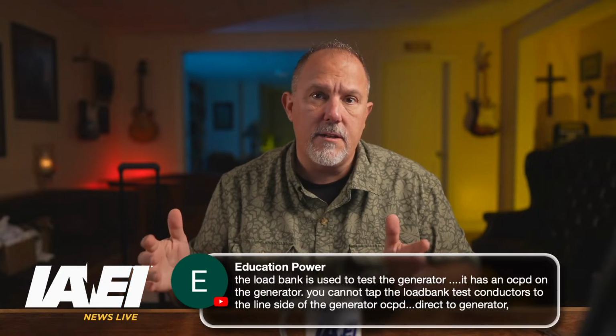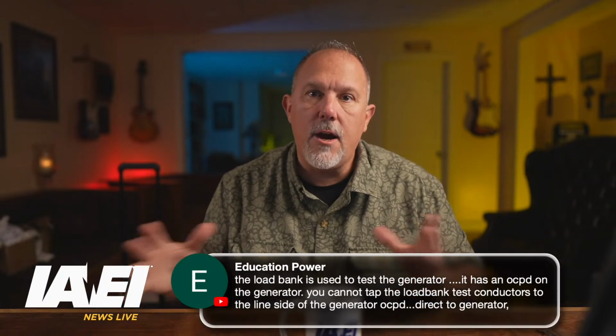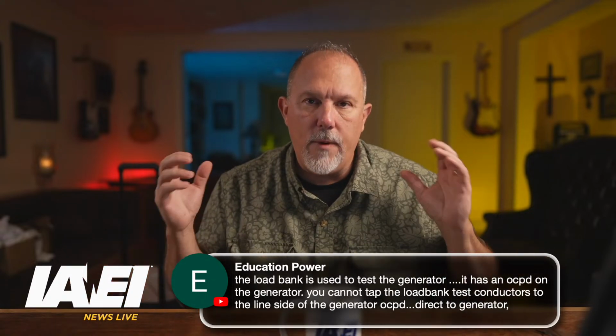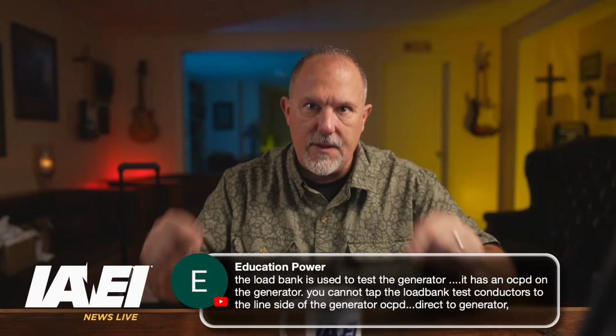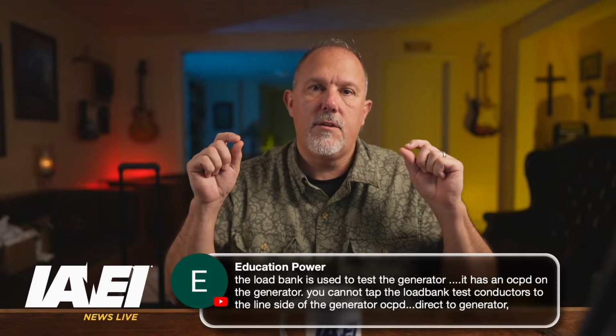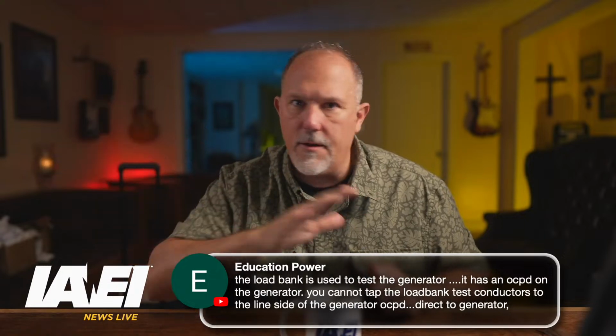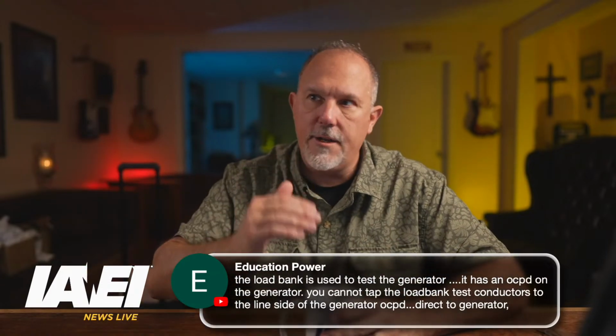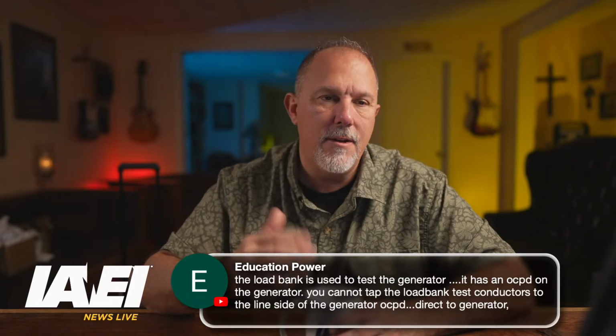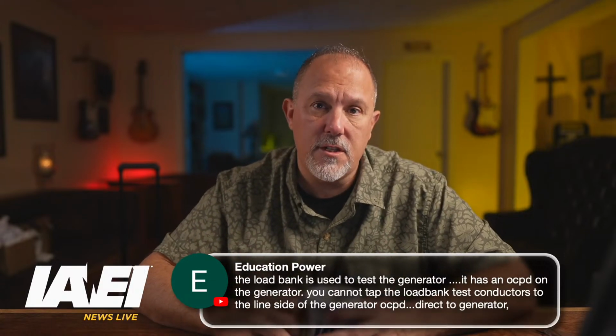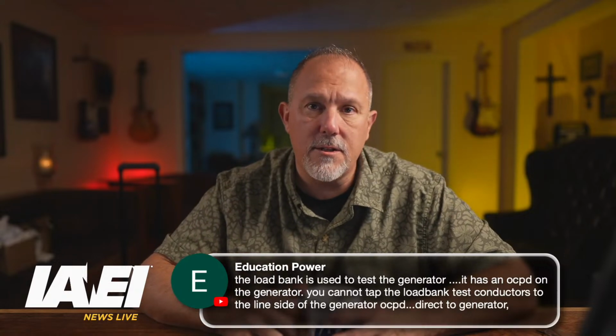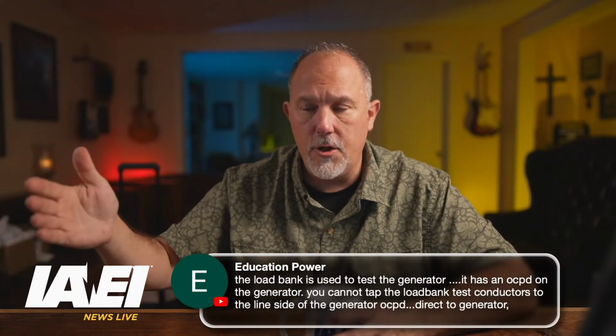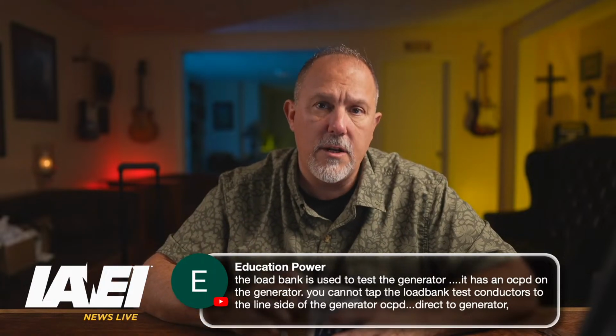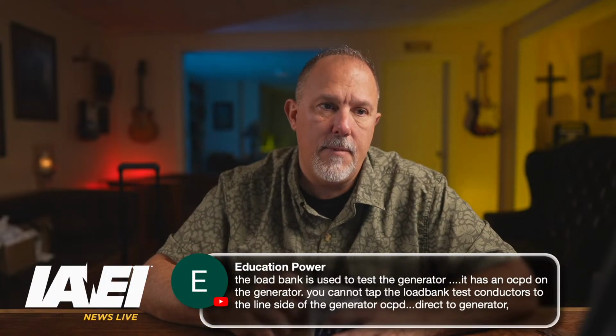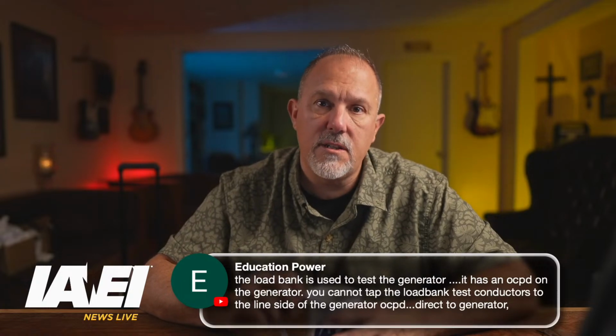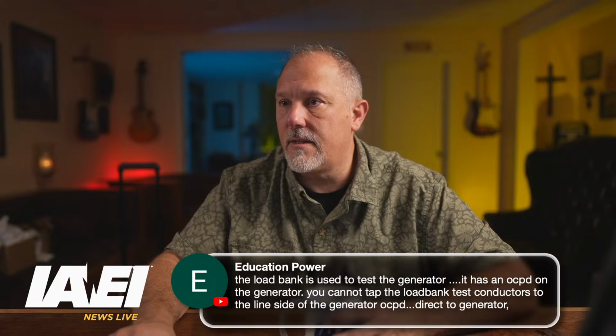You're doing something that is not a part of the permanent wiring. But when that generator is in place, it is a feeder. So you have to make sure that the conductor and all of that equipment is sized as feeders. But under that specific test scenario, it's an oddball. You have to just make sure that you're not going to overload the conductor, and that if there's a short circuit in your load bank, the circuit breaker is going to take that out. But again, it's under test scenarios. So I don't know what else to tell you.